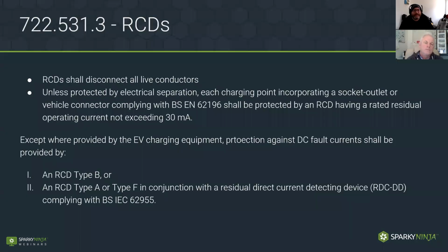Moving into RCDs, this is the other interesting area. It says it'll disconnect live conductors. That makes sense. And unless you've used electrical separation, you have to have each charging point incorporating a socket outlet or a connecting vehicle connector will have to have a 30 milliamp RCD. Okay, obviously electrical separation is isolated from Earth, so that shouldn't be necessary. Obviously, in all other scenarios, we're going to need a 30 milliamp RCD.